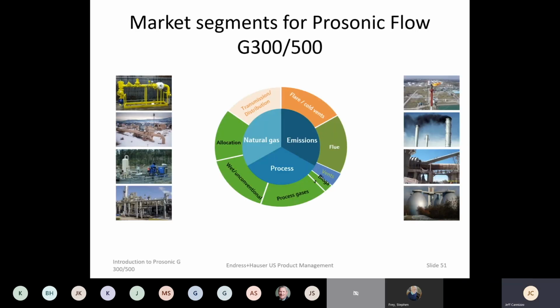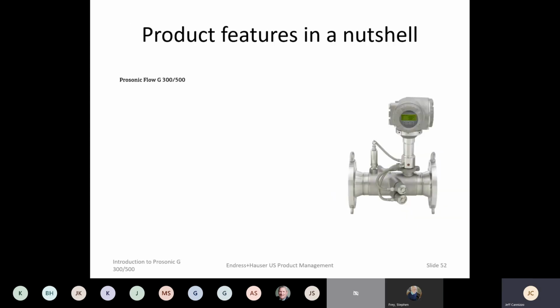So these particular meters are used in gas transmission, flares, and other types of processed gases where you need accuracy. Biogas, for example, which is typically a hot, wet, dirty gas. Thermal mass does not hold up well. Ultrasonic meters hold up very well in wet, dirty gases. So we do have some limitations. Pure hydrogen and pure helium cannot be measured with ultrasonic. They just don't exhibit the correct sound velocity profile.